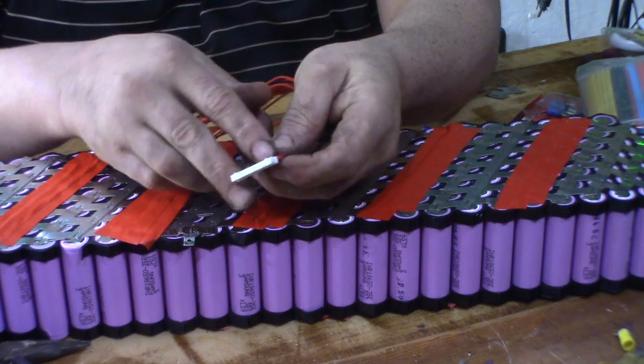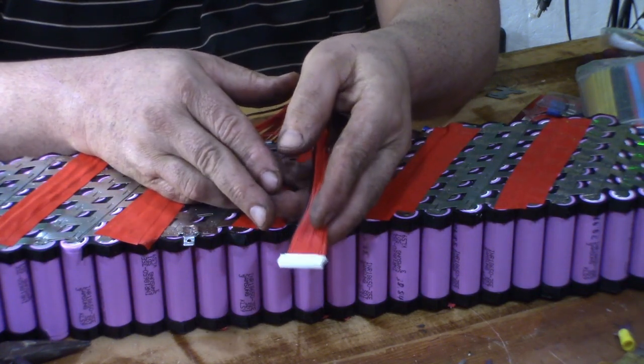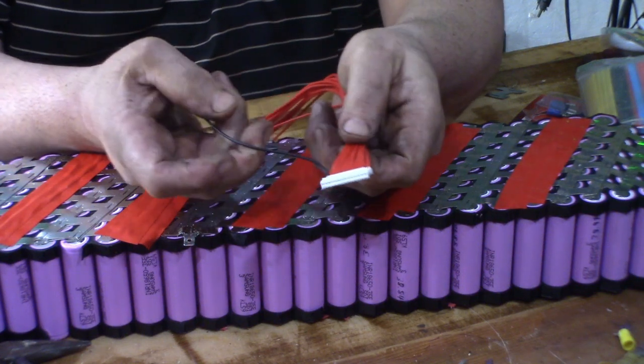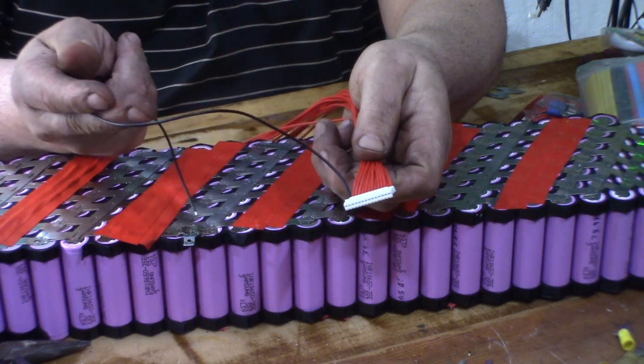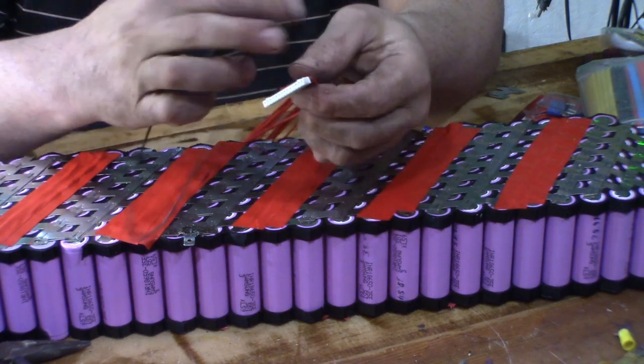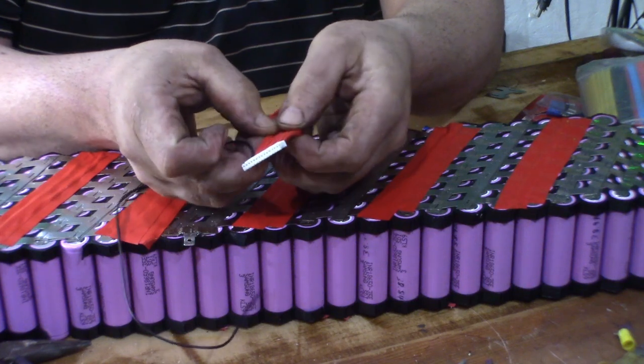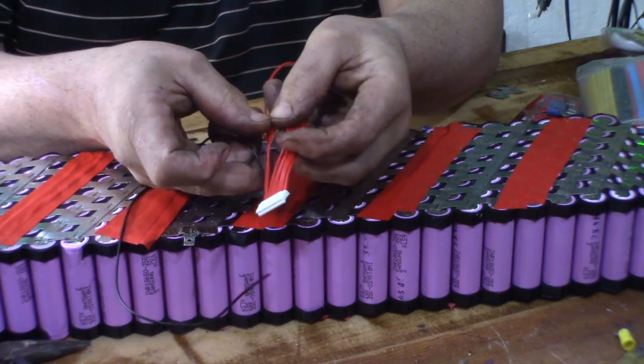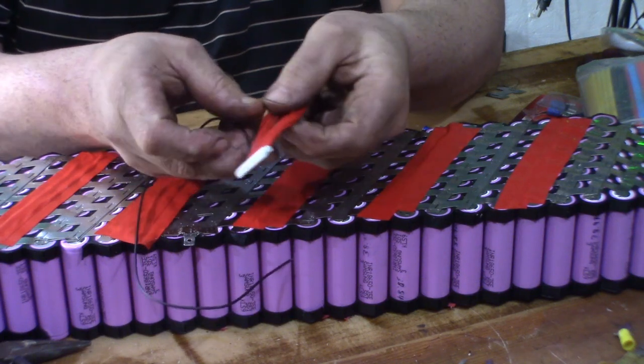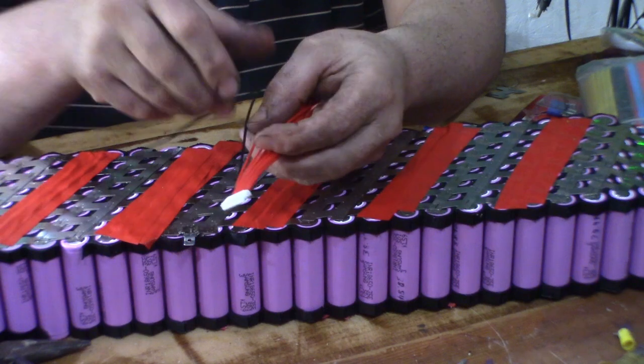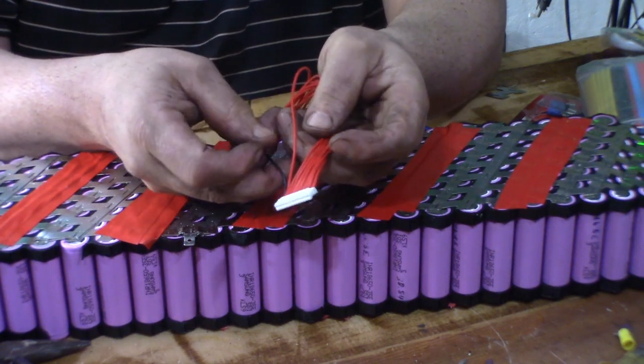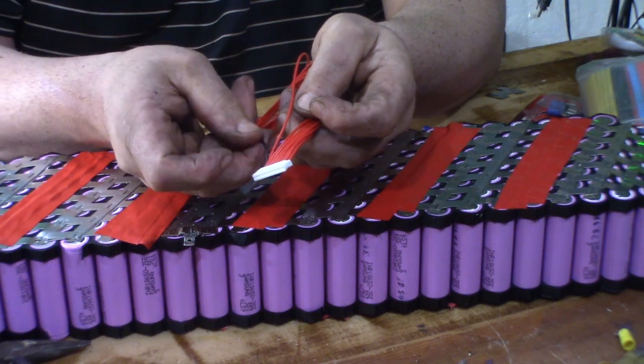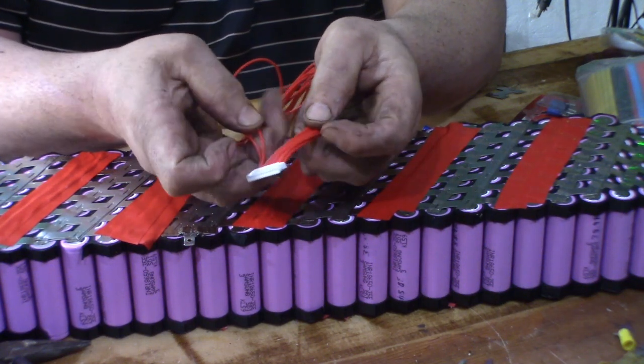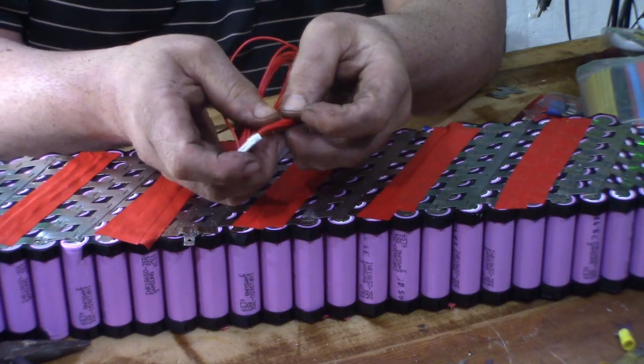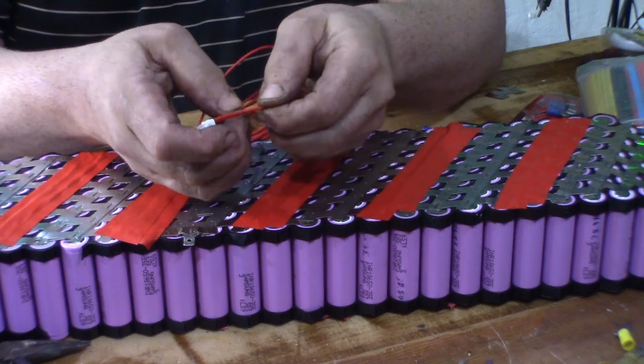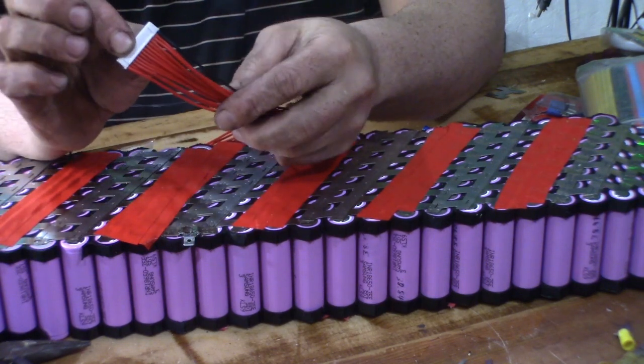When we put our BMS on, this is the plug side of the BMS. We've got a black wire that connects to the negative end of the battery, and then 13 red wires, one for each of the series connections. Going along the path from the black: first series connection, second, third, fourth, fifth, sixth, 7, 8, 9, 11, 12, 13 - 13 red wires and 1 black.